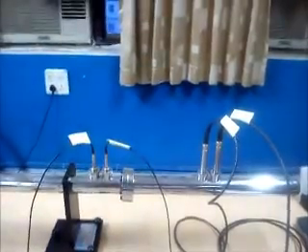So, ensuring everything has been measured, HC calibration and phase calibration have been measured. Now putting back all the microphones. Right now it is mic A, mic B, mic D and mic C. So putting the microphones back into A, B, C, D, we have to change the order of microphones 4 and 3, that is microphone C and D, and put them back into the standard position.